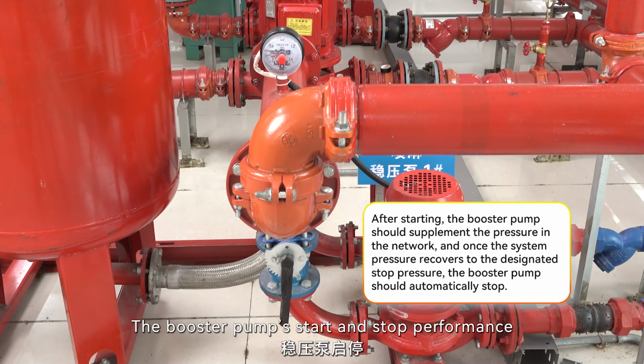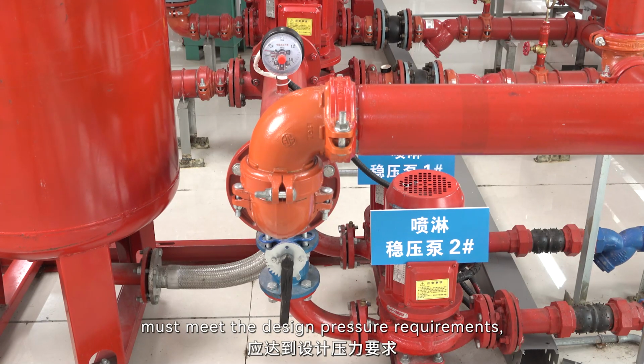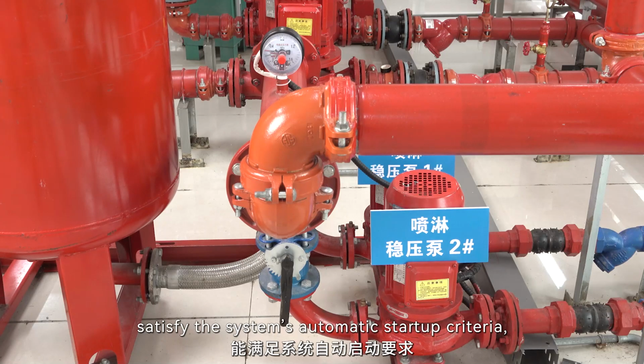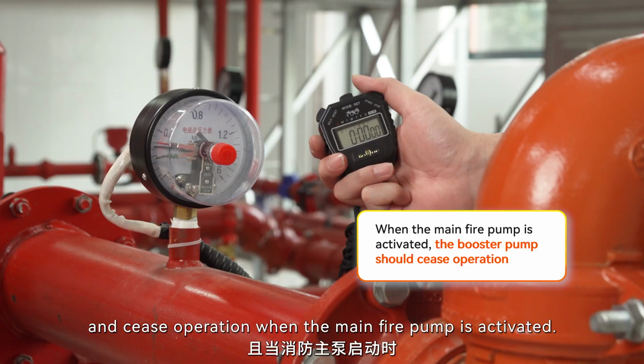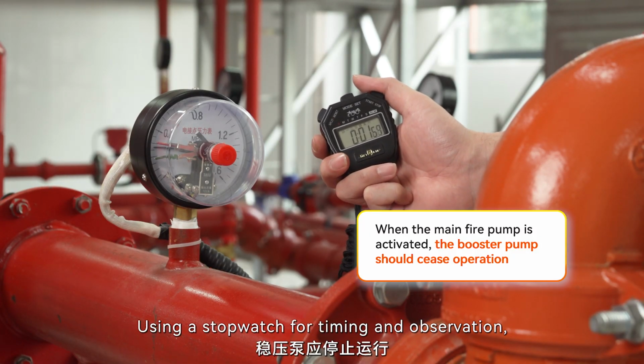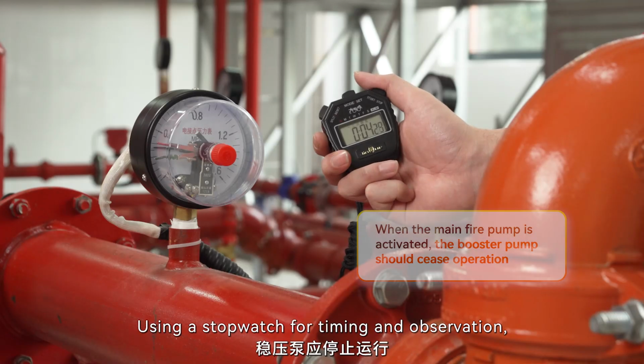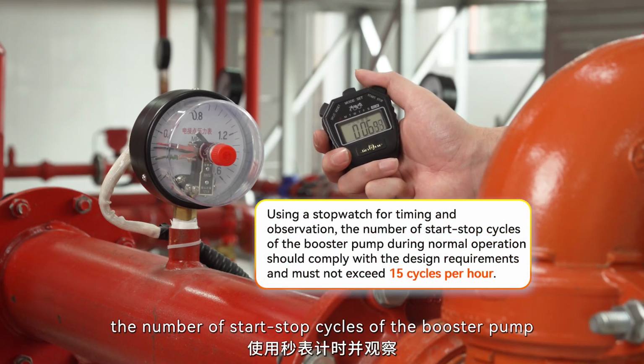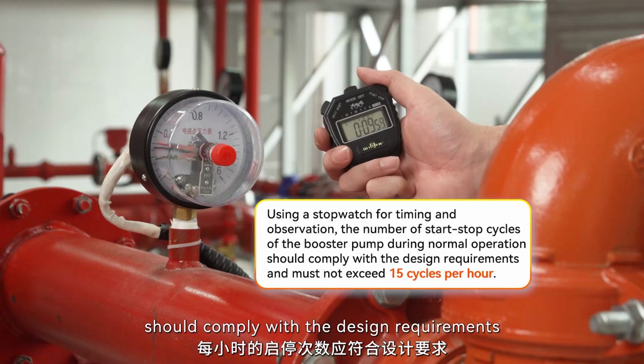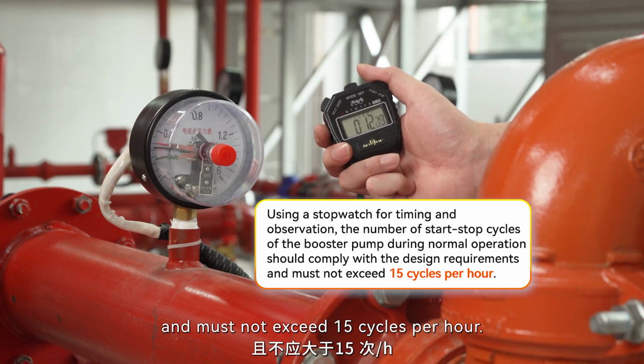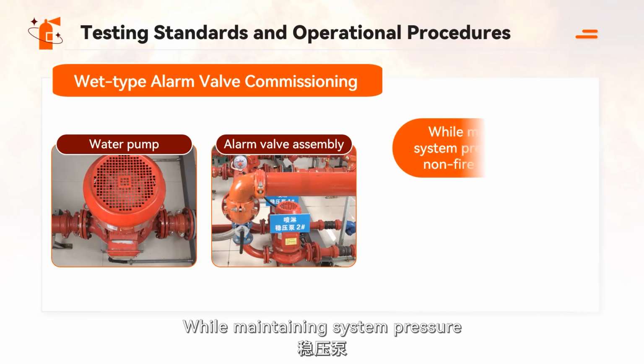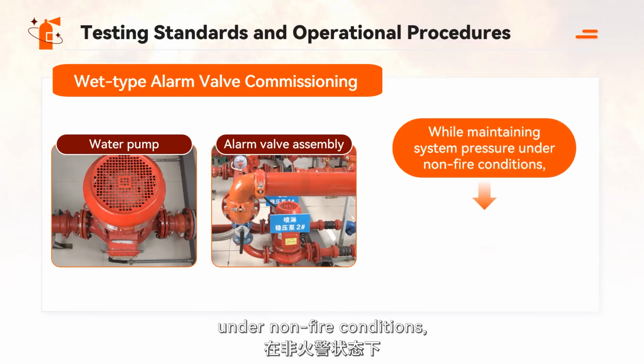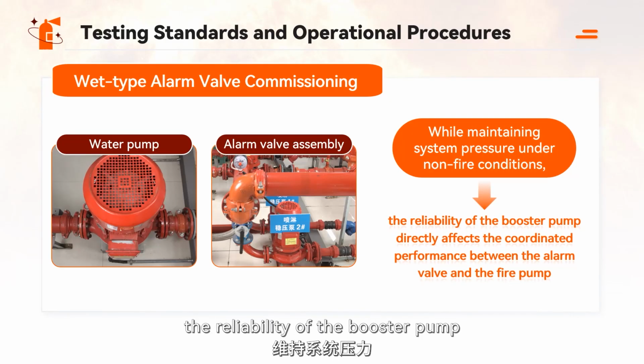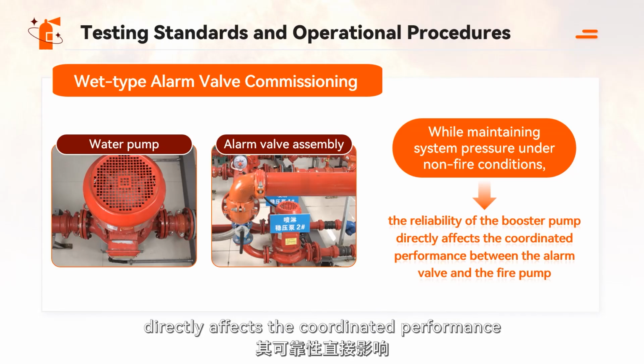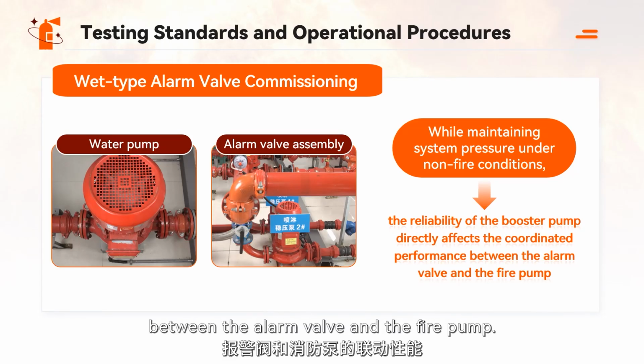The booster pump start and stop performance must meet the design pressure requirements, satisfy the system's automatic startup criteria, and cease operation when the main fire pump is activated, using a stopwatch for timing and observation. The number of start-stop cycles of the booster pump during normal operation should comply with the design requirements and must not exceed 15 cycles per hour, while maintaining system pressure under non-fire conditions. The reliability of the booster pump directly affects the coordinated performance between the alarm valve and the fire pump.